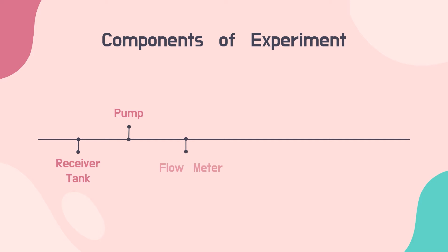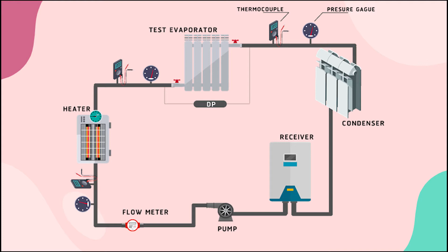The reservoir tank is a device that stores the liquid transferred from the condenser. The pump is a device that delivers fluid by suctioning it. The flow meter measures the flow rate. The heater is a device that imparts heat to something to be heated. The test evaporator is a device used to turn a liquid chemical substance into vapor. The condenser is a heat exchanger used to condense a gaseous substance into a liquid through cooling.